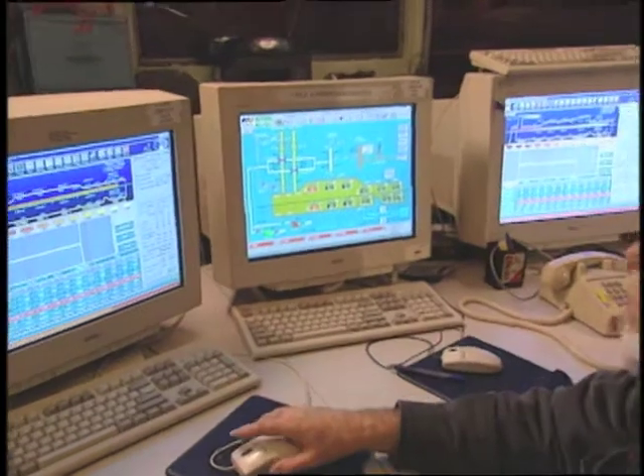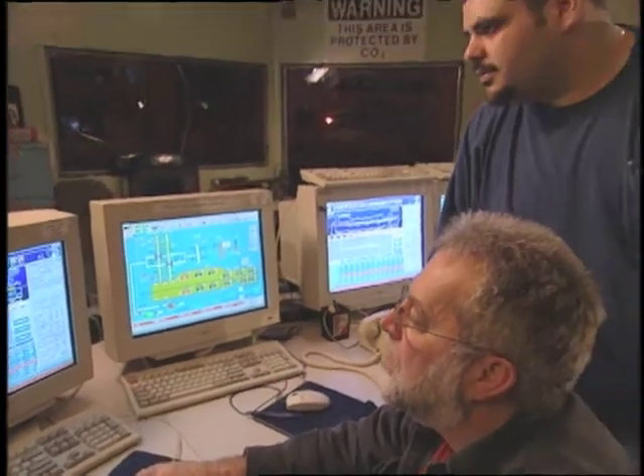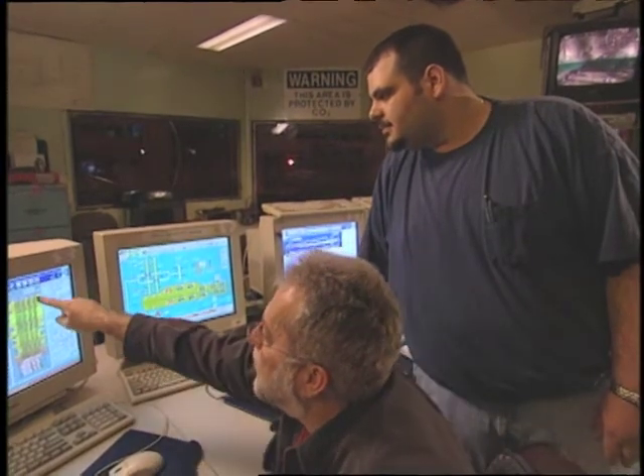Real good. The system itself, the DeltaV system, has software designs in it, safety features, where if we've got a problem out there, it'll shut the furnace down. If I go into the screens to find the problem, I get a delay light, and I go to that delay light, it takes me right to the problem. And then if I can't correct it, I call a mechanical or electrical. If it's their problem, I let them know and they go correct it before we shut down or anything.